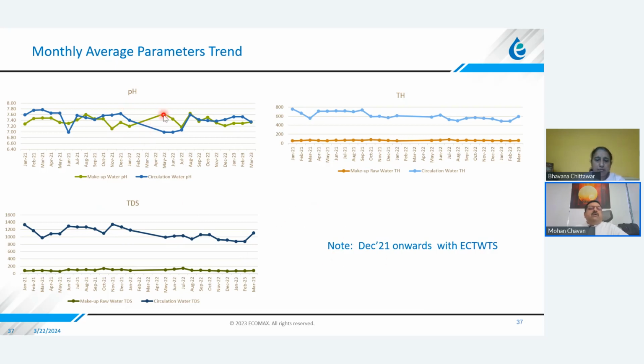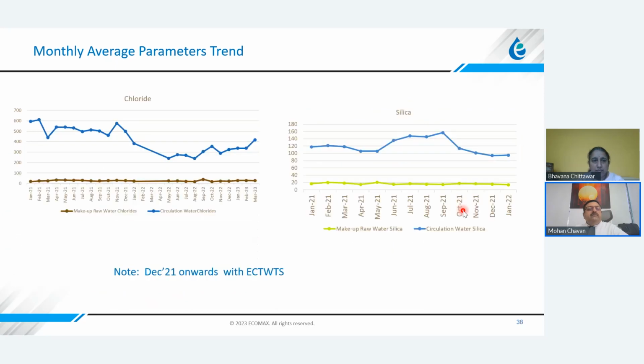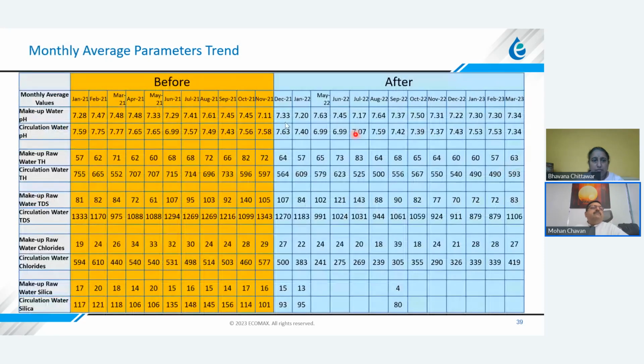Let's say December 21 onwards is when the electrolytic system is running. If you see here, pH is maintained, total hardness is lower than what it was before. Even the TDS is lower than what it was before. Even the chlorides, you will observe, are also reduced compared to what they were before. Even the silica has got a downward trend from here. These are some of the parameters before and after implementation of electrolysis-based water treatment.